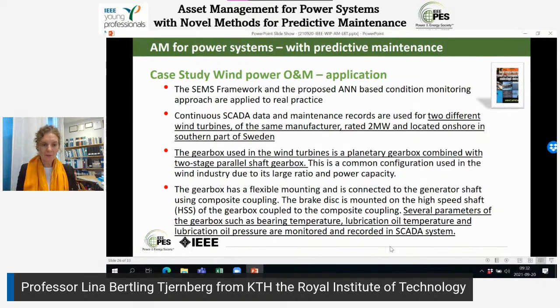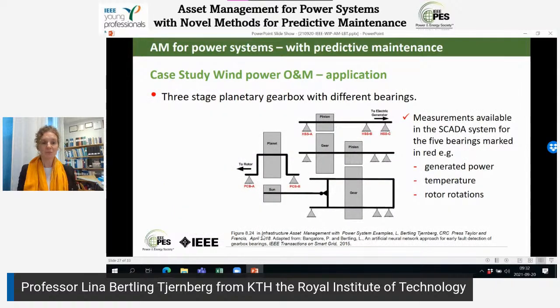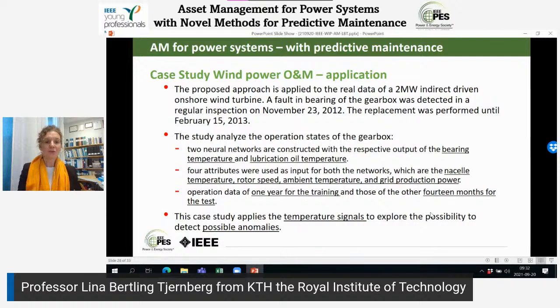We are collecting several parameters, for example the bearing temperature, the lubrication oil, and the lubrication oil pressure, which are monitored and recorded in the SCADA system. Here you see a graph explaining the gearbox, and in red the different locations where we have the measured data. It's five bearings, and we have information on generated power, temperature, and rotor rotations. So in this application, we are applying it, as I mentioned, to the two megawatt data.